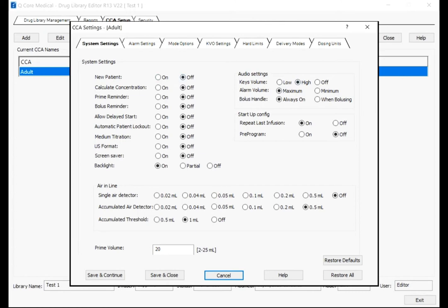The new patient for EMS, we leave that off. The next one will be calculate concentration. We normally see that turned on just so that you can calculate drugs on the fly outside of the drug library. We'll go all the way down to the format. Most all these others we see are off in the EMS world. Format. We'll do the U.S. format and the screensaver. Most folks do like to see that on. It's just another feature that you know while you're infusing you can see on the screen, and it does save some battery life.